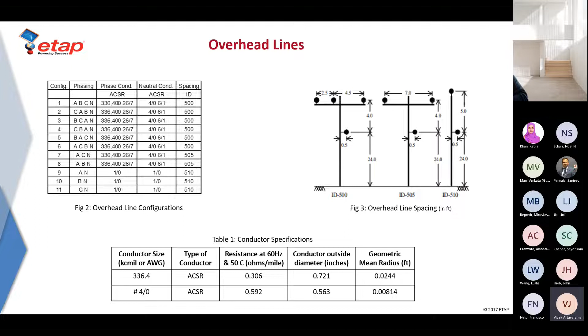For the overhead lines, interpreting the data sheet, there's information on phasing, where A, B, C, and N are in different orders, what the phase conductor material is, what the neutral conductor material is, and what the spacing ID is. For example, configuration 2 has a spacing ID of 500, corresponding to a section where phase C, A, and B are positioned with the neutral in specific locations. Based on the distances the lines are from each other, you end up with different configurations and impedance matrices. This is modeled in ETAP, where, for example, I have taken configuration 1.